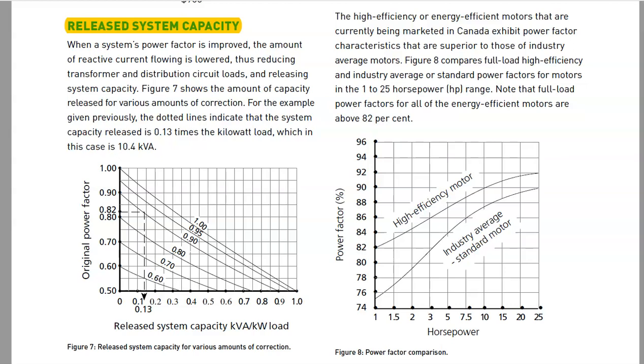When most people looked at it, they said, look, this is what your system is right now. This is how many amps you're running continuously. This is the size of the system. I went in there and rented, for a case of beer from a friend of mine, a power quality analyzer, which allows me to test for power factor and things like that. I put that on, took a look at the power quality and the power factor, and I realized that if I could correct their power factor, we could easily fit all that additional load on there, because the additional load was just a hair over what would be required to kick up to the next service.